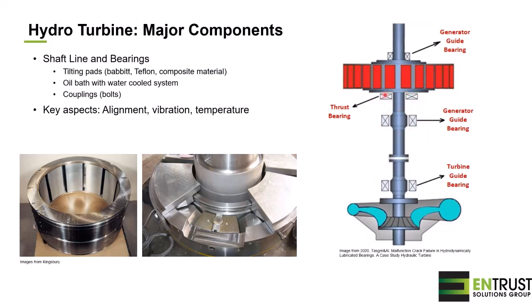This, for example, is a location where we will find a significant amount of oil bath. The bearings will be in an oil bath, and the oil bath will have to be cooled, for example, by water to prevent overheating of the bearings. The bearings use most of the time tilting pads. They can be made of babbitt. Now it's more and more often that we find Teflon or composite material for that.